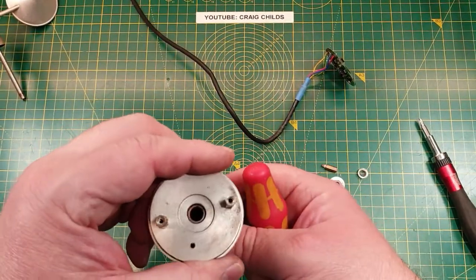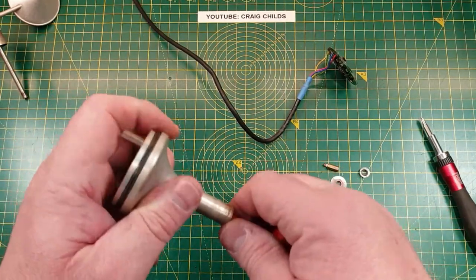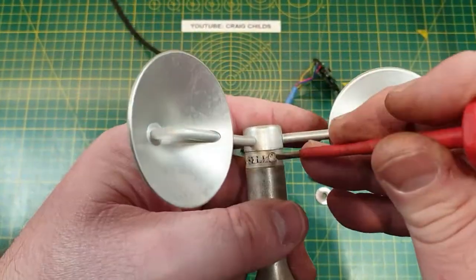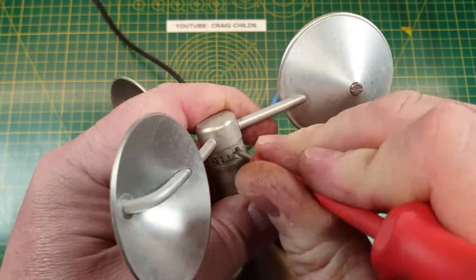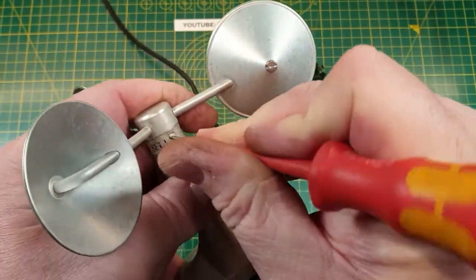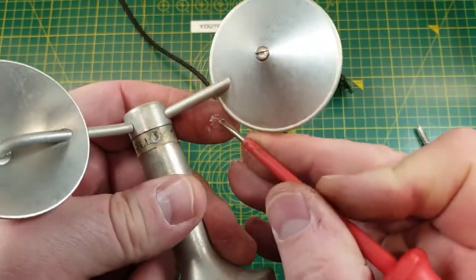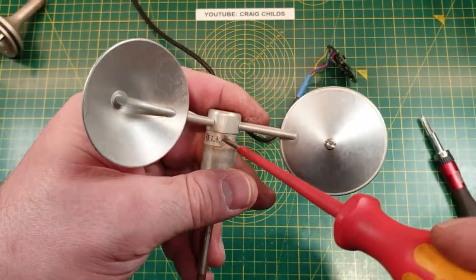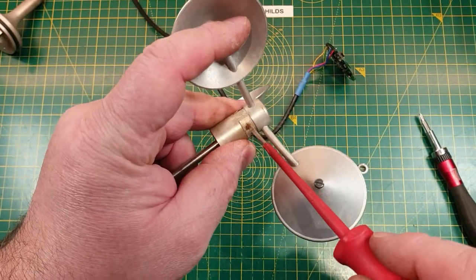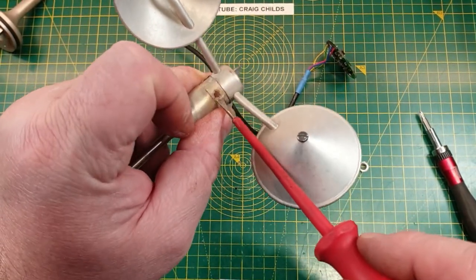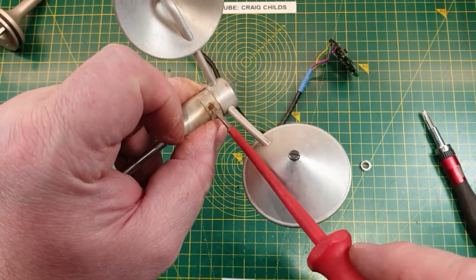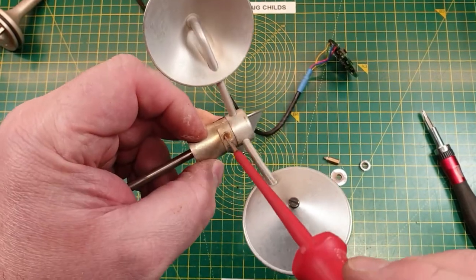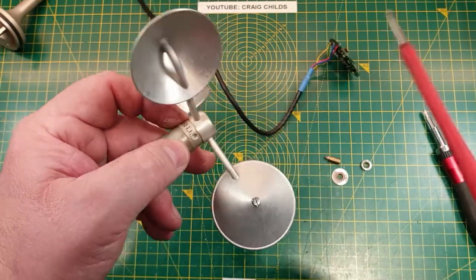So the bearings have failed. So that's been the main failure mode. That's what's caused the unit to stop working. But what's led to the bearings failing appears to be some form of water ingress. That looks like the end of the screw. And I think it's snapped off. So I'm getting this white powder here, that'll be a mixture of rust from the screw and a bit of oxide on the aluminium. As it appears that that's lost its head. Now I know this one's lost its head because when I was initially diagnosing the fault, I tried to remove this screw and the head came off straight away. And that's because the corrosion had already taken a good hold here. So I could try and drill these out, but I'd have to put that on a bench drill and I don't have that here. So that's maybe a job for another day.